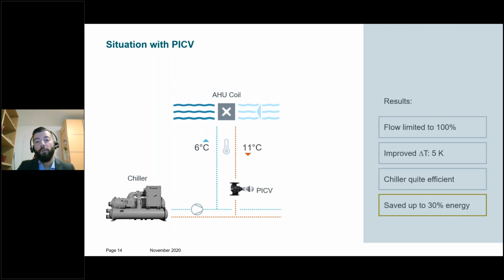And a first and very good mitigation measure is to use PICVs, because thanks to the dynamic balancing compensation, the flow in the terminal unit is always limited to 100%. Therefore, the energy transfer is more efficient with a delta T of, say, maybe 5% higher. The pump is not using as much electricity and the chiller works quite efficiently already.